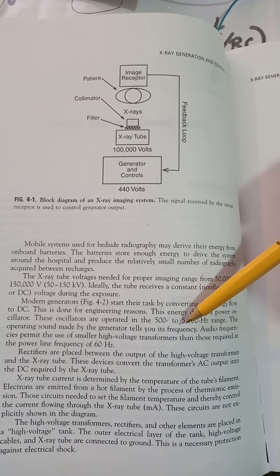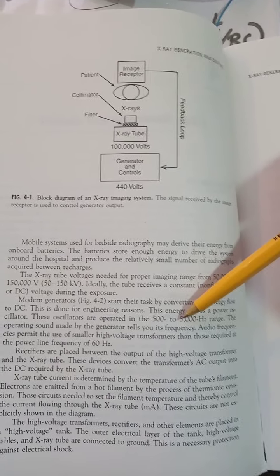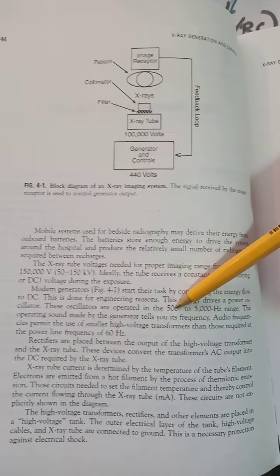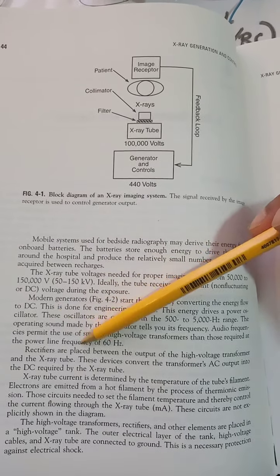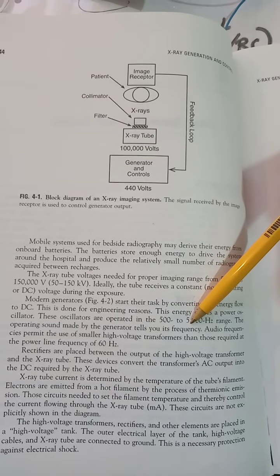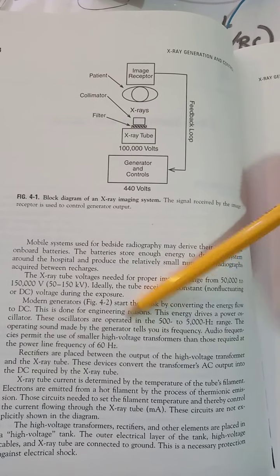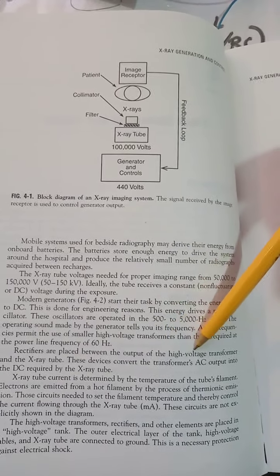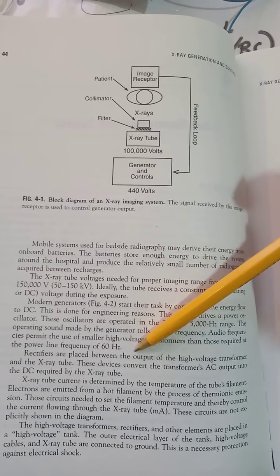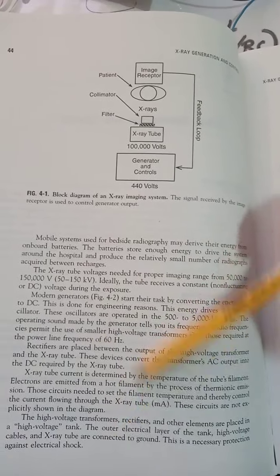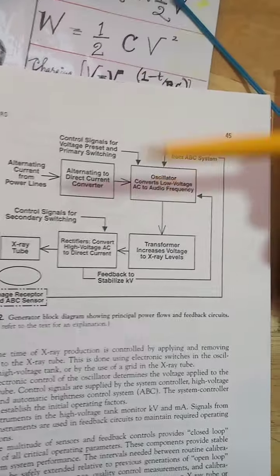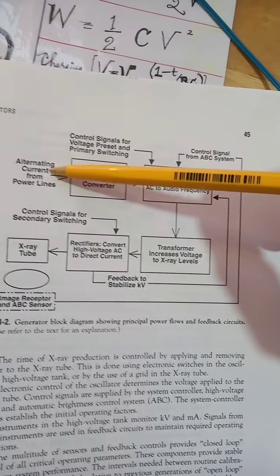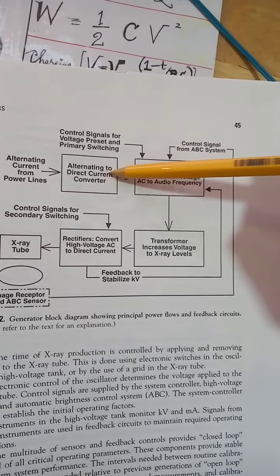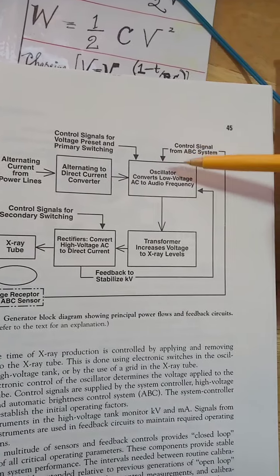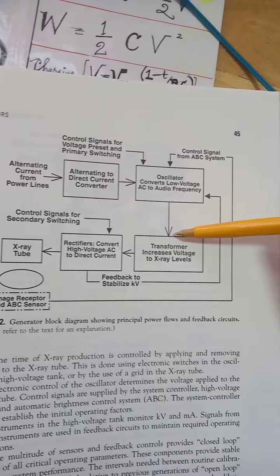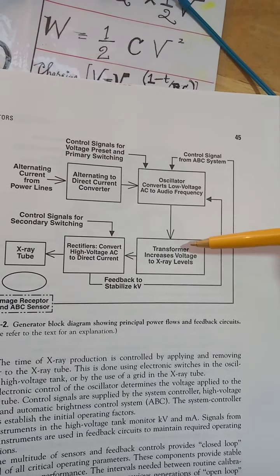So audio frequencies permit the use of smaller high voltage transformers than those required at the power line frequency of 60 hertz. Rectifiers are placed between the output of the high voltage transformer and the X-ray tube, and the devices convert the transformer's AC output to DC. I think what it's telling you here is best explained with this diagram, where you get the AC current from the national grid, and it's converted to DC here by the hospital, and then it's sent to the oscillator where it converts low voltage AC to audio frequency, and that audio frequency goes to the transformer to step up the voltage to X-ray levels.